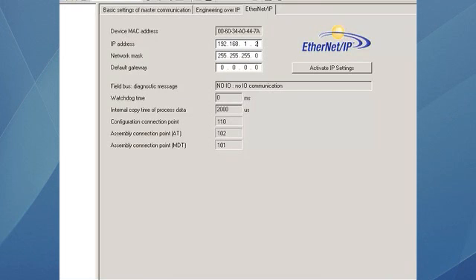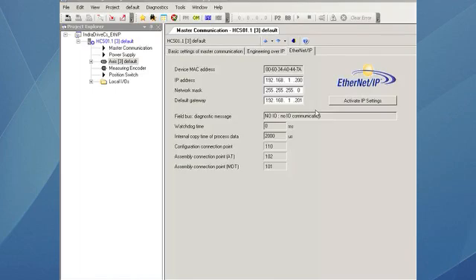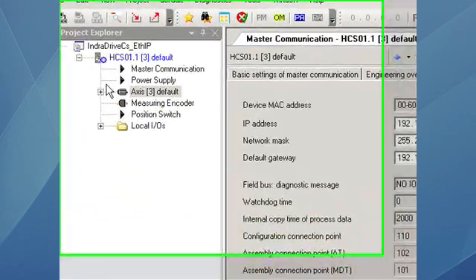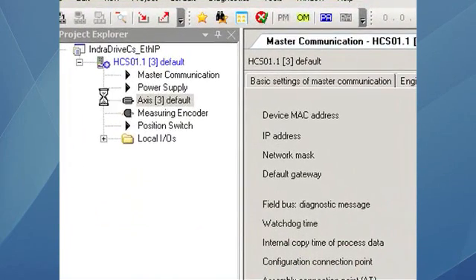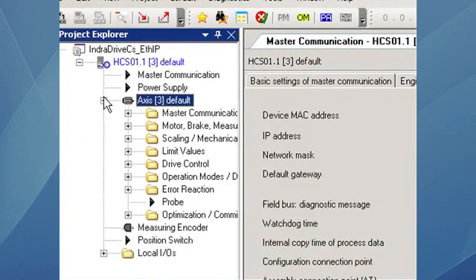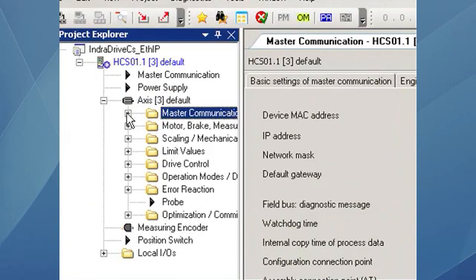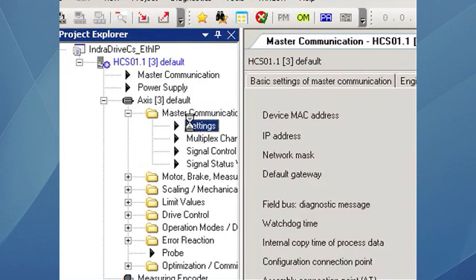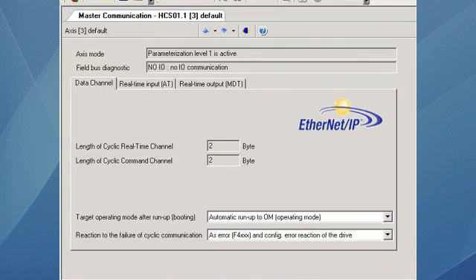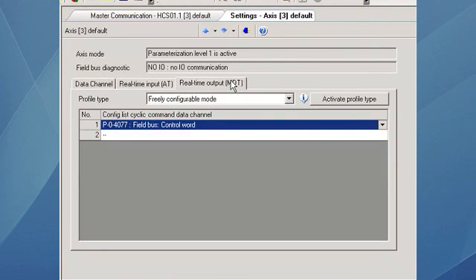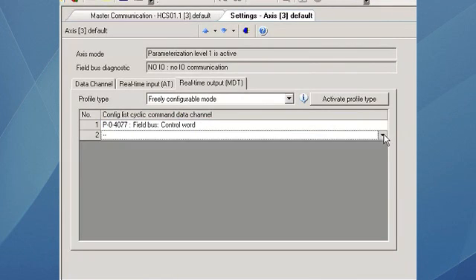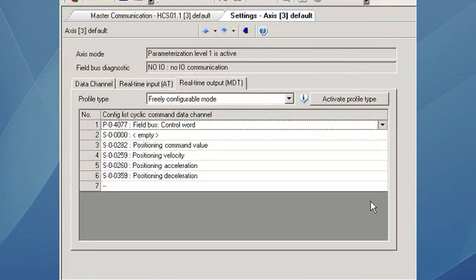After we do that, we go to the master communication settings and configure the inputs and outputs coming from the master. In this case, the outputs of the master are going to be the commands. We will set the field bus control word, positioning command value, positioning velocity, positioning acceleration, and positioning deceleration.